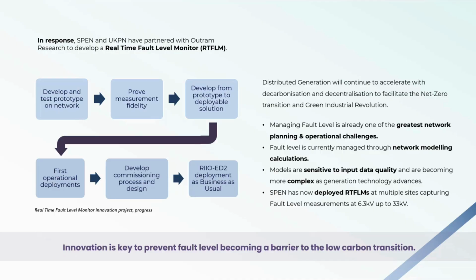So firstly, the work we did to prove the measurement fidelity, so some independent testing and verification that we've done to prove that. We've then redesigned the device to take it from prototype to an operationally deployable solution. We've completed our first operational deployments, and in total, SPEN has deployed fault level monitors during the course of the project at 9 or 10 different substation sites now, capturing fault level measurements from 6.3 kV up to 33 kV distribution voltages. So during the course of this, we'll be developing the commissioning process and design, and we're now looking to deploy as business as usual during the course of the rest of RIIO-ED2.